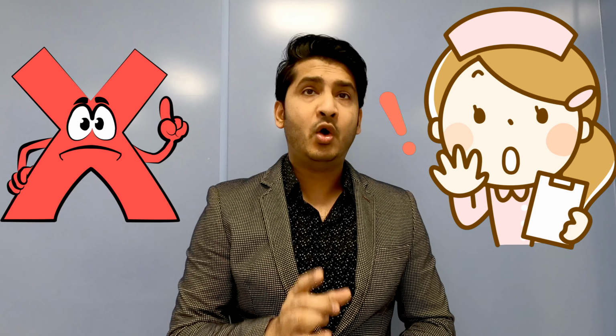The next check is alarms. I always say alarms are your best friends. To start with, we have to make sure that alarms are on. Under no circumstances should your alarm be off, as it can be detrimental for the patient and can compromise patient safety. Very rarely, due to situations like end of life or palliation, alarms can be put off, but it has to be documented properly. Once we check that alarms are on, we have to set the appropriate alarm limits.